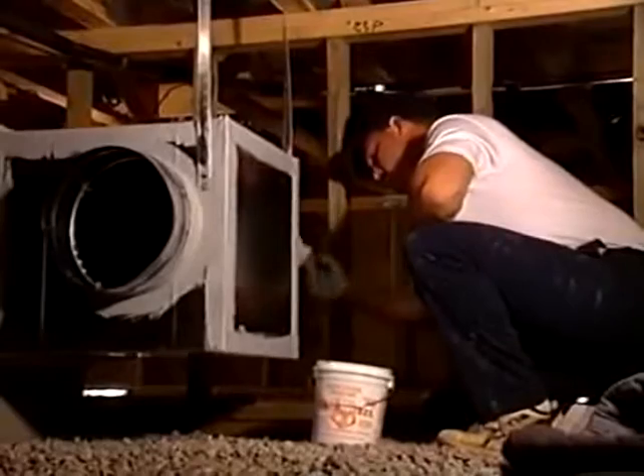The techniques for sealing ductwork are the same, whether you are using metal or flex or duct board. Seal every joint along the way. Reinforce with fiberglass mesh tape, and you will reduce air leakage and increase comfort. If we looked at ductwork the same way we look at our plumbing, we could learn a lot from our friends, the plumbers. Because in plumbing, we wouldn't want to have a plumbing system that was substantially leak-free, nor should we want a duct system that's just substantially leak-free. We want it to be leak-free, period.